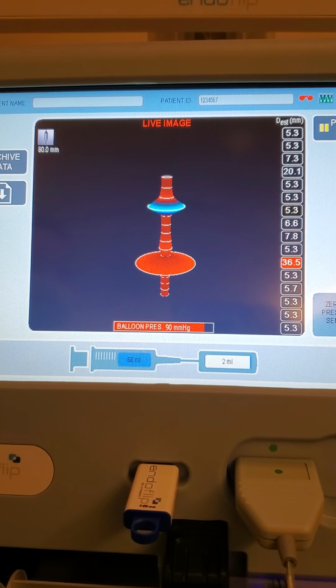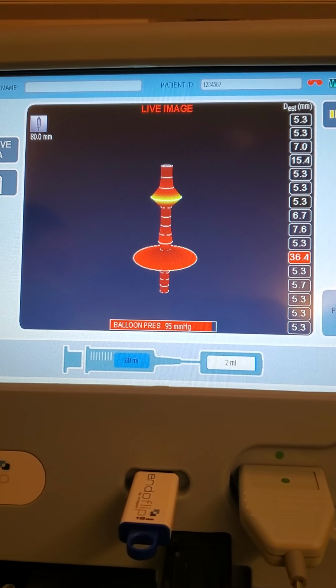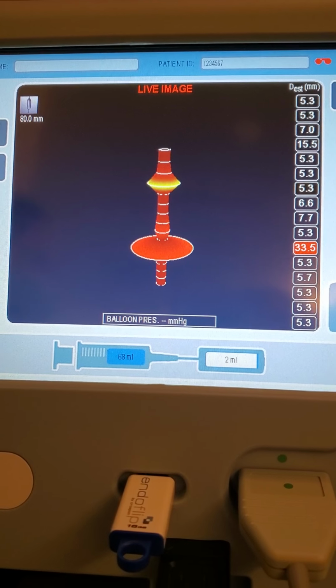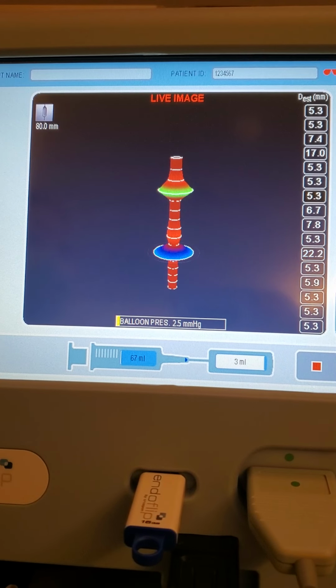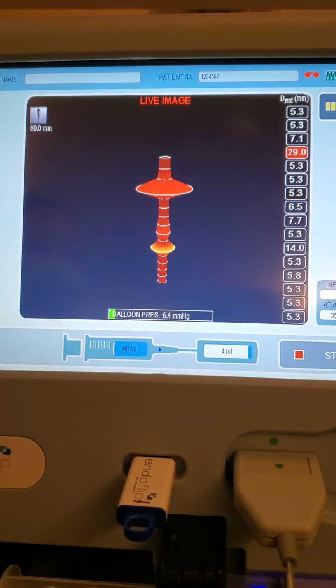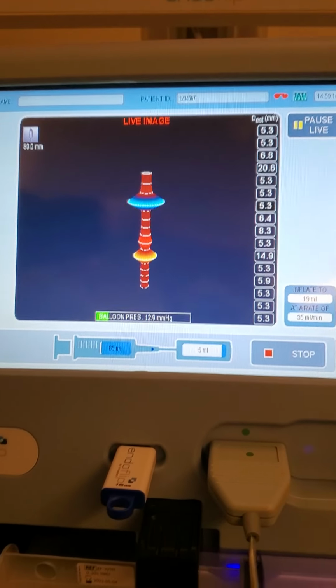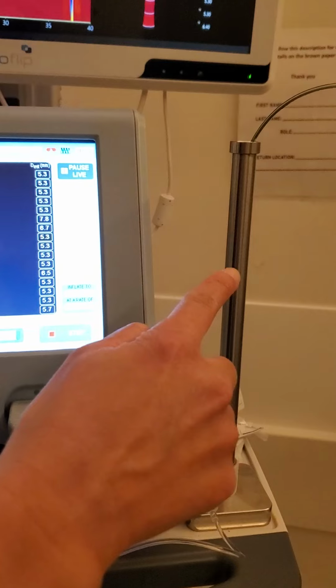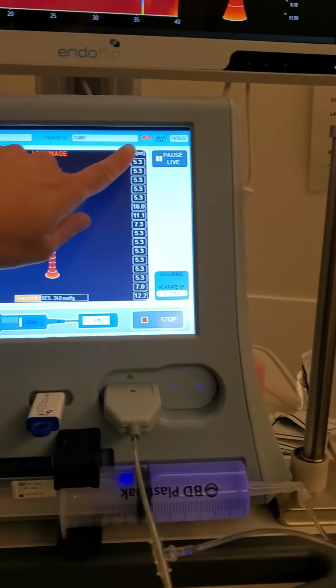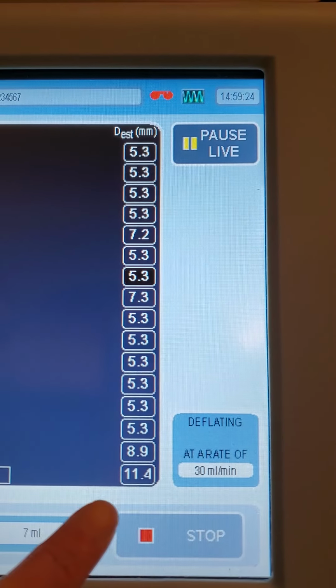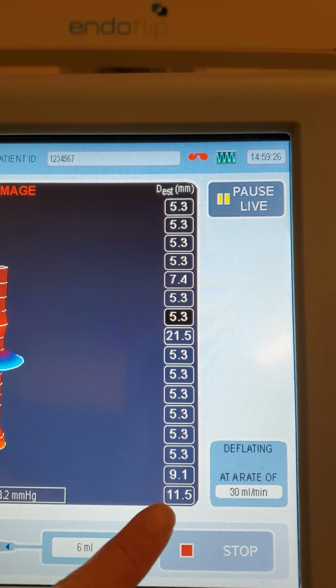This step takes 3 or 4 minutes or so, but you don't need to babysit it. You can leave and go get the patient or do what you need to do. At this point, what's happening is the machine is pushing the liquid into the balloon, and it's testing each of the sensors. There's 16 sensors on the balloon, and each of these numbers is the sensor reading.